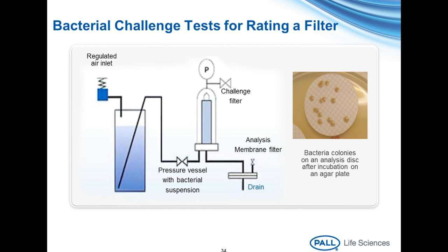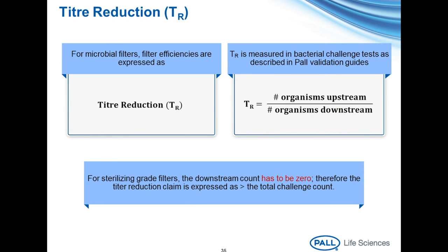This is a performance-based test, and that's why it's important to evaluate performance under your conditions of actual use. For a filter rating test, the bacteria would generally be suspended in a buffer or similar fluid. For the process-specific test, the bacteria would be suspended in the process fluid. There are two possible outcomes to a bacterial challenge test: either absolute retention or some degree of retention, which is a measure of filter efficiency. Filter efficiency is expressed as titer reduction—a ratio of the total number of bacteria in the influent divided by the total number of bacteria in the effluent.